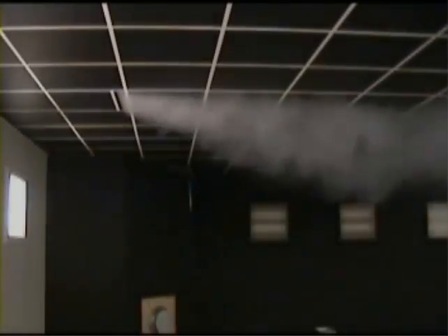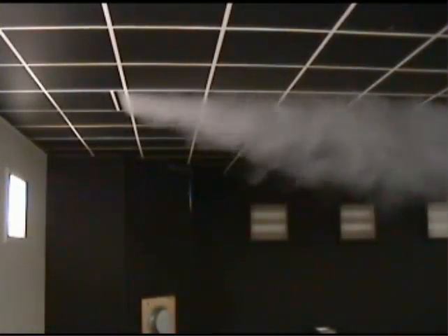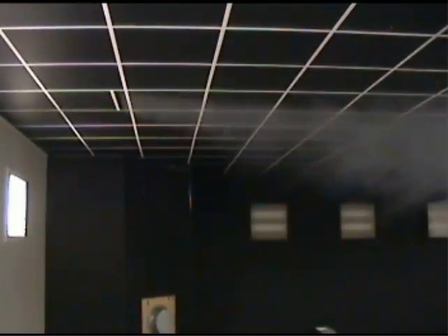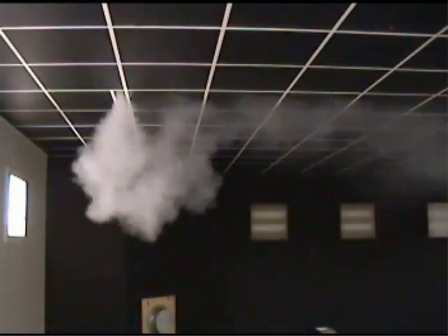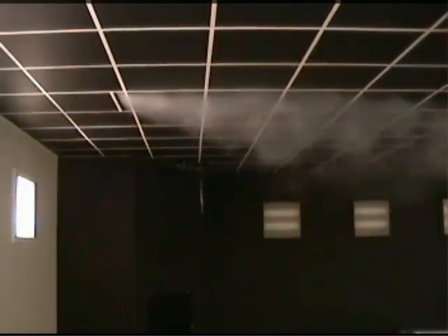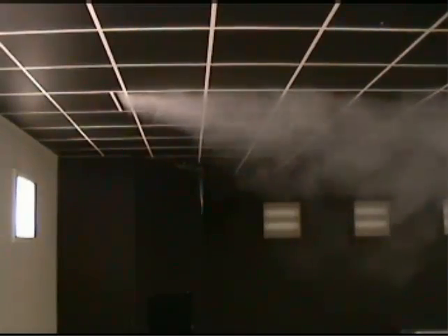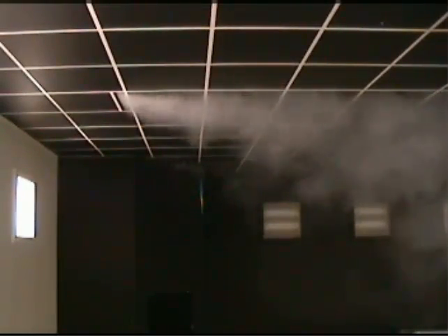This smoke video shows the change from horizontal air pattern to vertical occurs when the supply air temperature reaches a designated level. When the change occurs, the pattern is converted quickly to minimize the effects of drafts in the occupied zone. During heating, the air blows back toward the glass at approximately 15 degrees so the unit can be mounted into the room at a distance of about 18 to 24 inches. In addition to comfort, this system reduces energy costs as all the warm air is effectively discharged down the glass during heating.